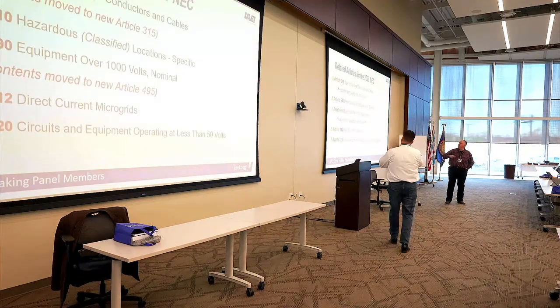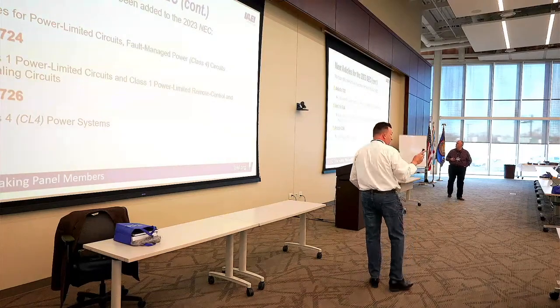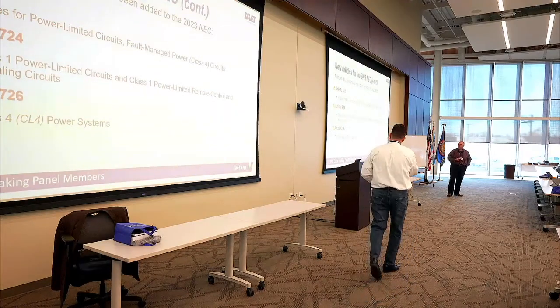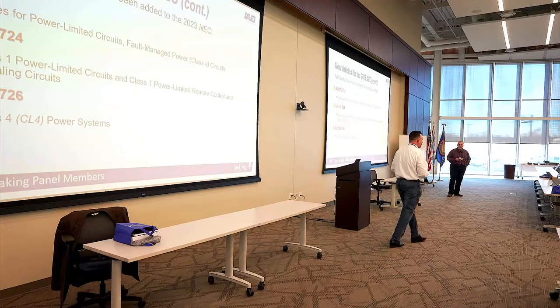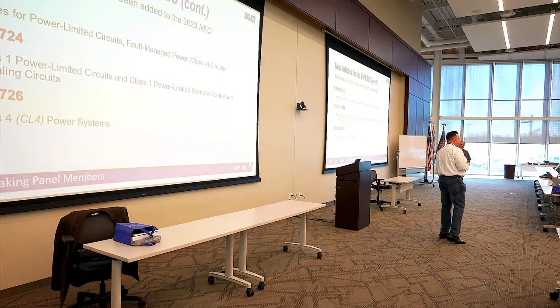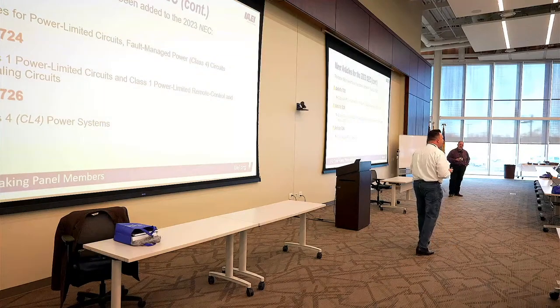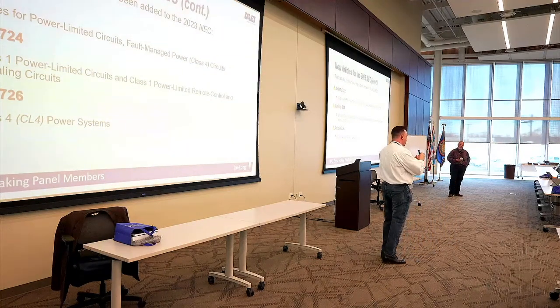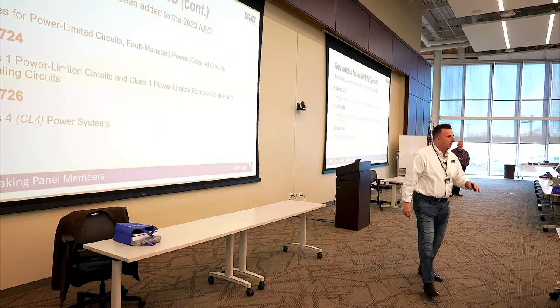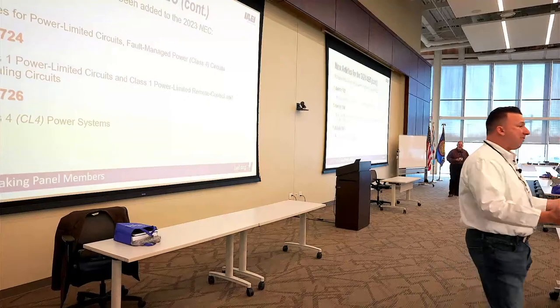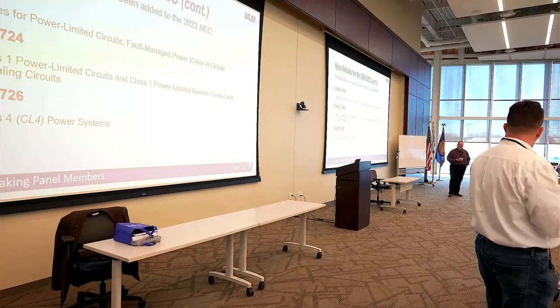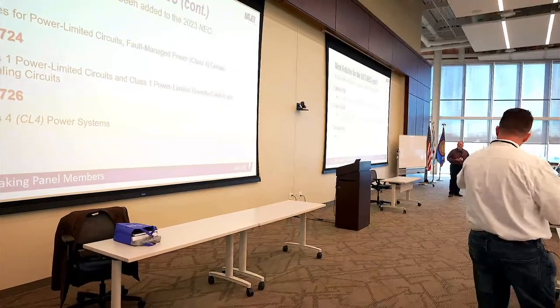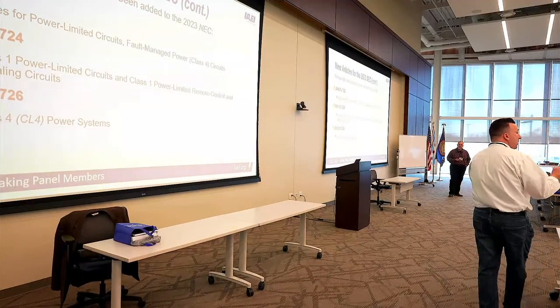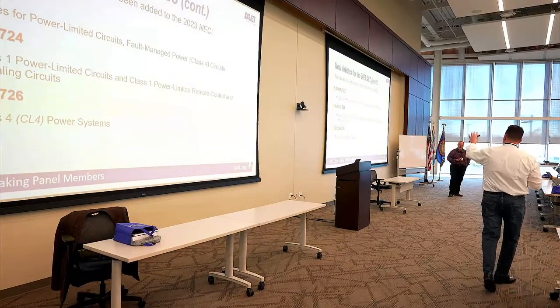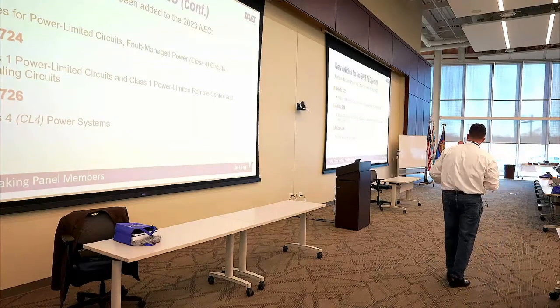Let's go back to that for one second, Tom, because I want to talk about article 724 real quick too. What article 724 did - you'll see it's power limited circuits for class 1, probably not as common as you might think. We took that out of 725, which is strictly class 2 and 3 now. Power limited circuits went into new article 724. Non-power limited class 1 circuits - well, they really have been, but it wasn't really clear - are treated like regular circuits now because they're not limited. So you won't see non-power limited circuits separately; those are just like regular circuits, chapters 1 through 4 wiring. So again, a lot of work went into that 722, 724 stuff.